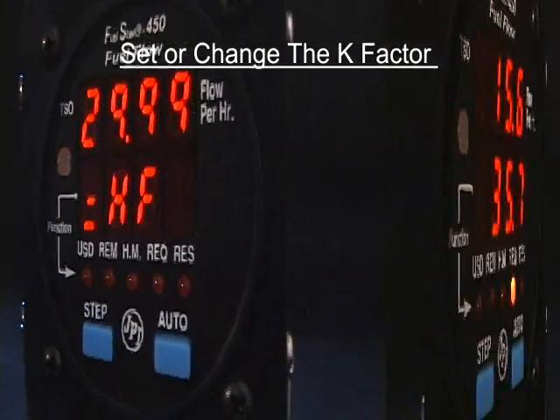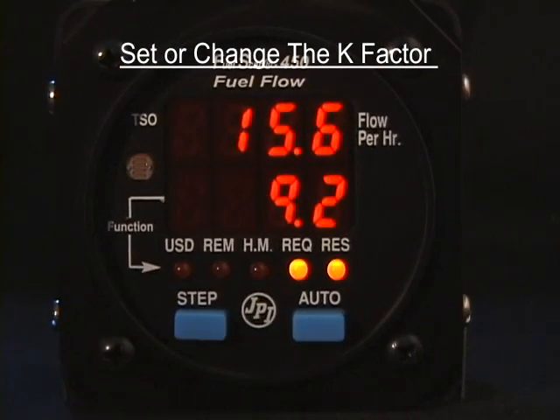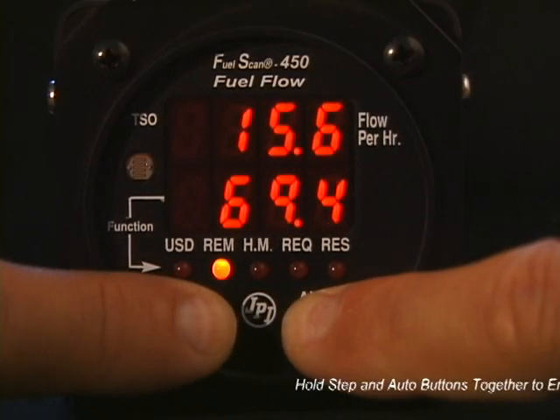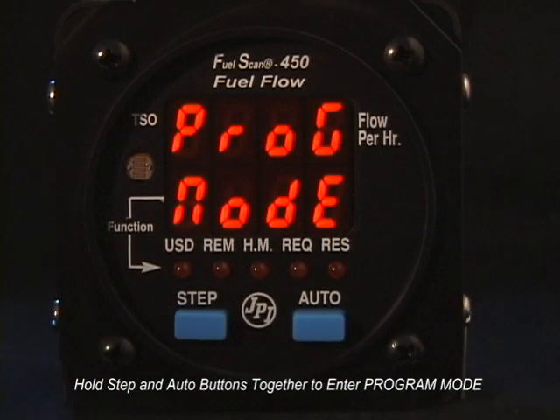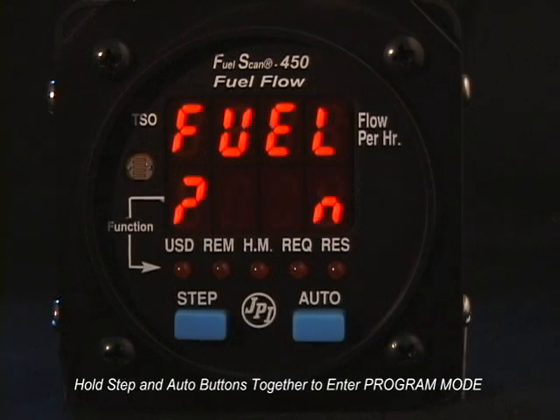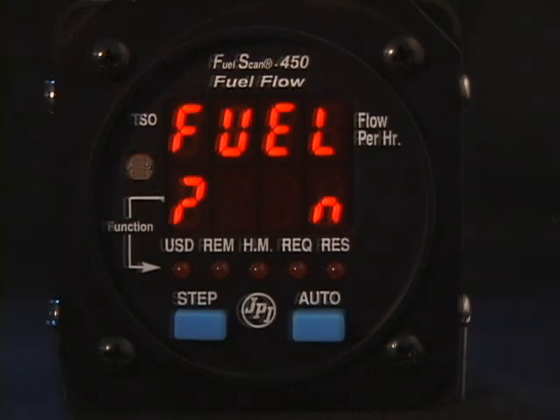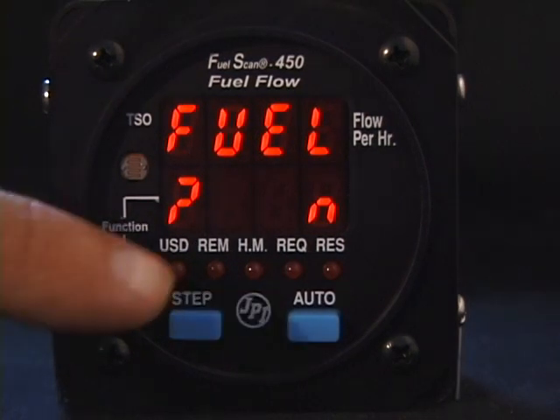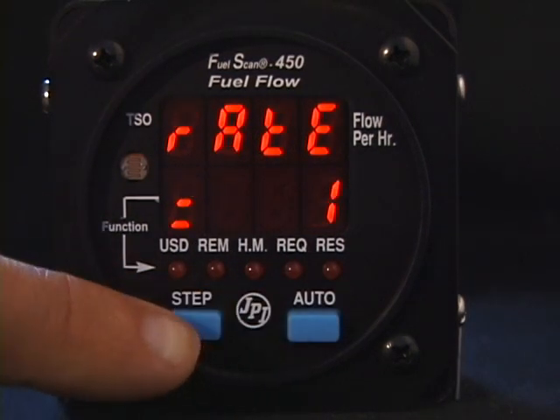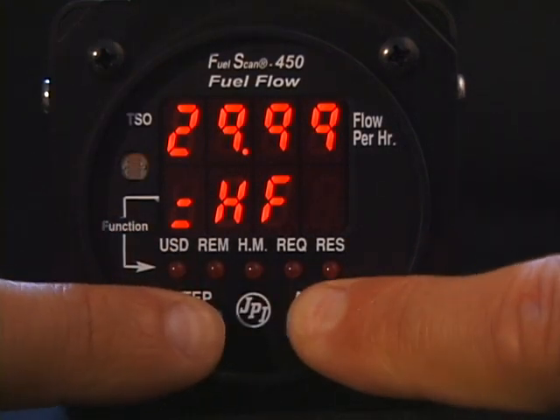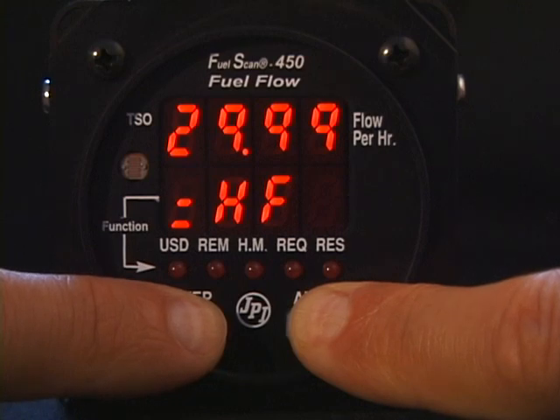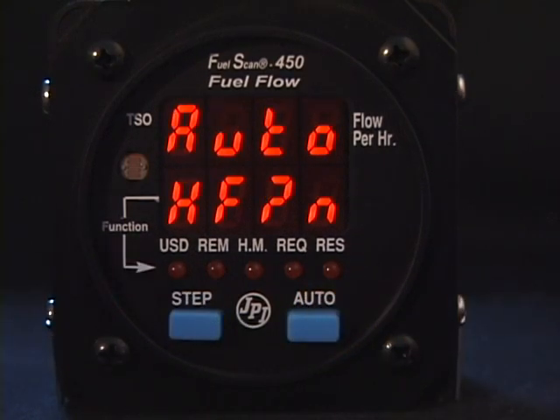This is how you set or change the K-Factor. Hold both the Step and Auto buttons simultaneously for a few seconds until you see the words Program Mode and then Fuel No. Tap Step twice to see the current K-Factor. With the current K-Factor shown, hold both Step and Auto until you see Auto K-Factor No.